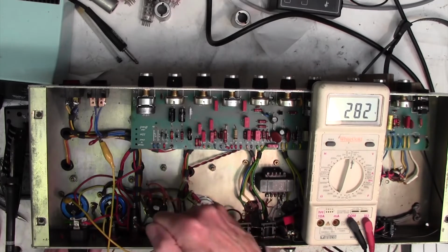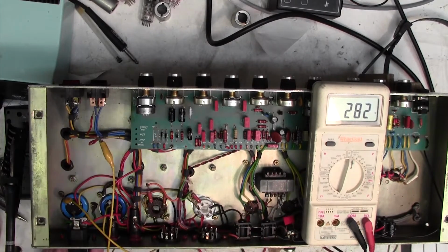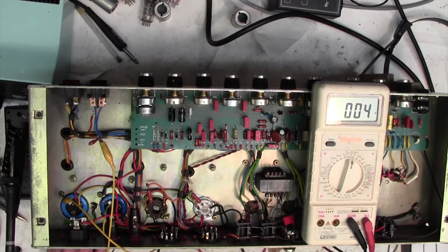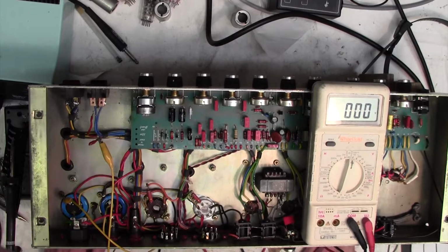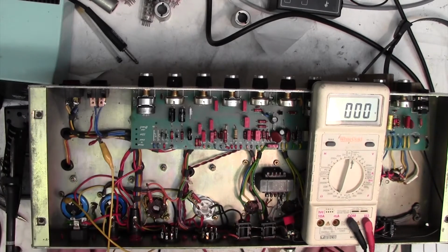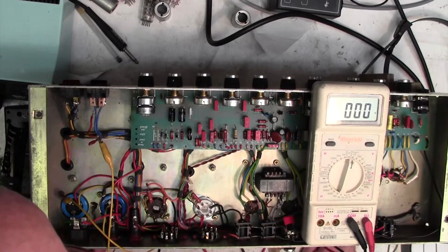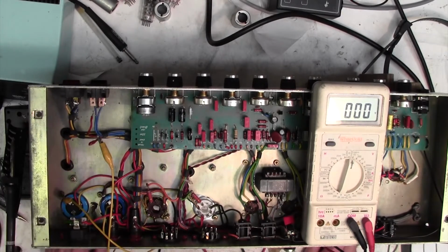I don't think it's anything to do with the voltage selector being wired incorrectly, because we only have a few choices there anyway. We have 240, 220 and 120, and when I changed it to 220, the voltage came up in exactly the proportion I'd expect. I'm certainly not going to go to 120 because that will give us double the voltage. So I don't think it's the voltage selector or the tappings on the transformer.